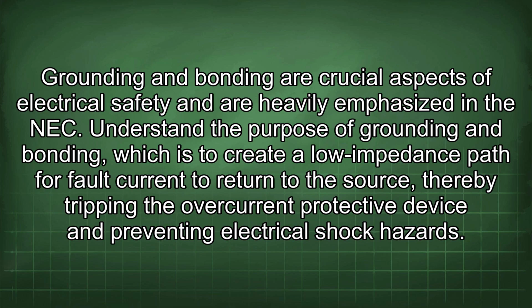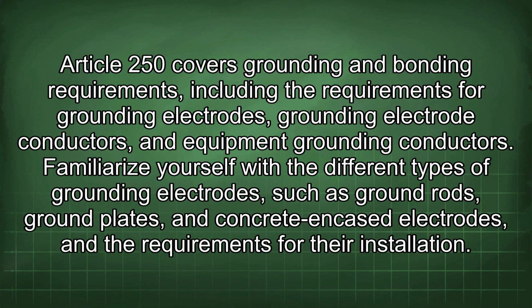Grounding and bonding are crucial aspects of electrical safety and are heavily emphasized in the NEC. Understand the purpose of grounding and bonding, which is to create a low impedance path for fault current to return to the source, thereby tripping the overcurrent protective device and preventing electrical shock hazards. Article 250 covers grounding and bonding requirements, including the requirements for grounding electrodes, grounding electrode conductors, and equipment grounding conductors. Familiarize yourself with the different types of grounding electrodes, such as ground rods, ground plates, and concrete encased electrodes, and the requirements for their installation.